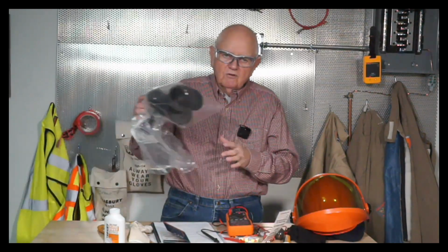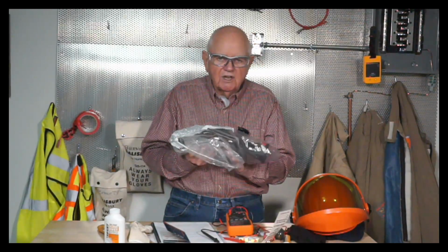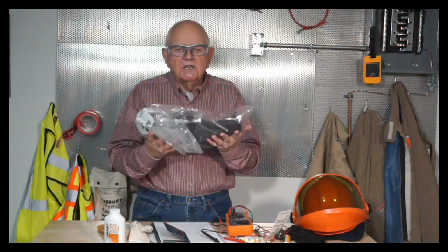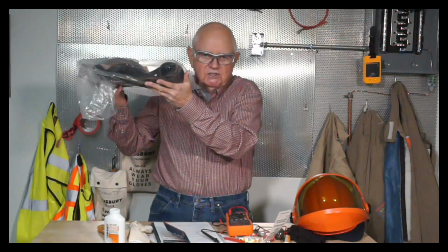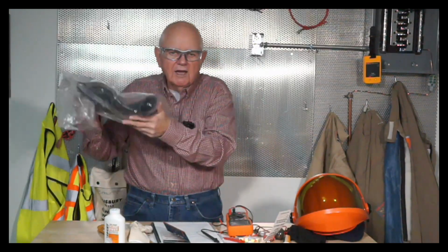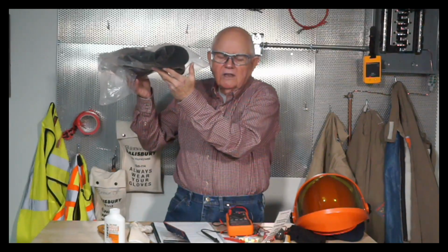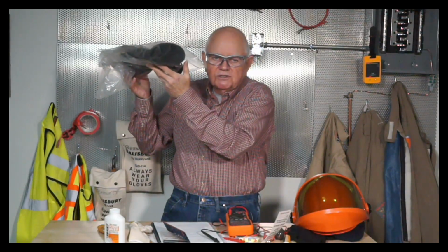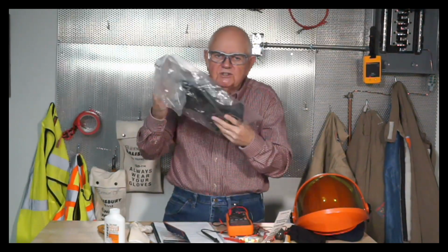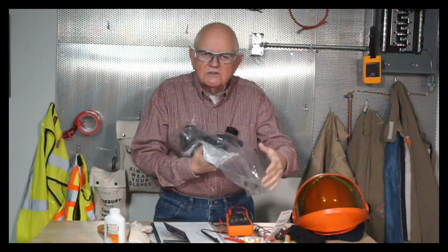First of all, I'm going to have to inspect my rubber gloves. I make sure that they have the proper test dates on them. These are brand new gloves. They're still in the bag. They were tested on January 1st of this year. I put them up on the shelf, and I can keep them on the shelf until December 31st. I then issue them. I take them out of the bag, give them to somebody to go use them.